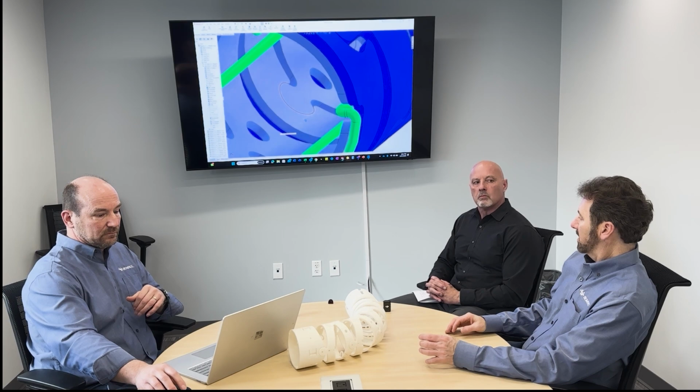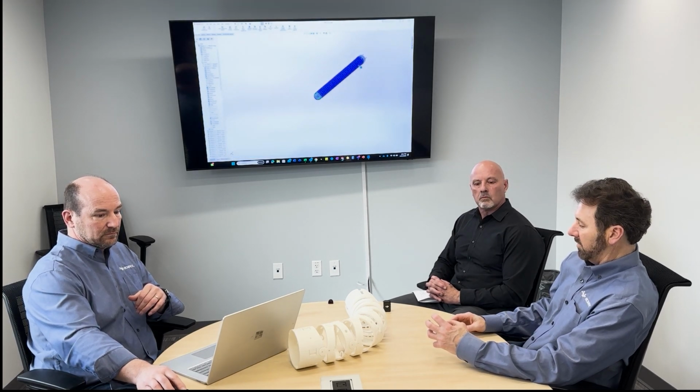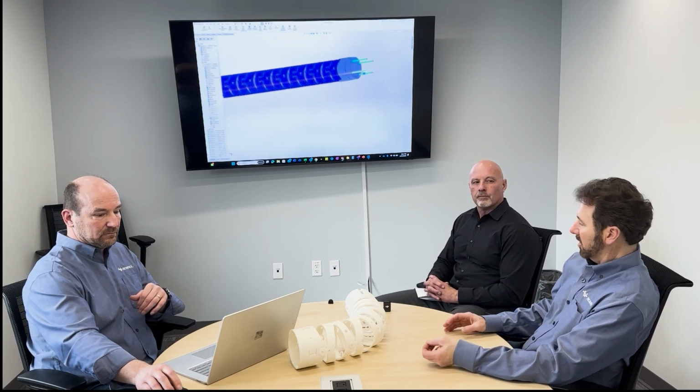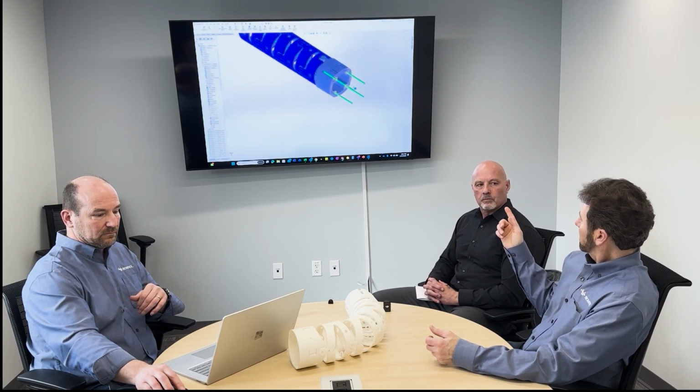Sure. So we can then put onto the end of this, what you're seeing right here, you can put on the distal end. You can put whatever you want. You can put a machined part, you can put a plastic part, you can put another part that would hold your camera, your working channel, LEDs, and on the other end you can put something that holds the coil pipes that you need, and the rest of your laser cut hypotube, braided shaft. So now you've got this section that can be put right in between that gives you the articulation. But then you are attached to another longer section.